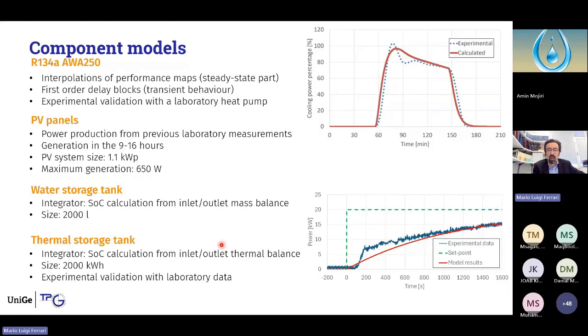For the water storage tank, it was 2000 liters, and on the basis of an integrator that we implemented, we have the calculation of the state of charge from the inlet-outlet balance. Then for the thermal storage tank, the same, for the hot water for the cooling side, for 2000 kilowatt hour in this case. Here on the right side of the slide, you can see a comparison of the model results with the experimental data. For sure, it's not possible to recalculate the specific oscillating behavior that we have at the beginning of the startup. However, we have set the delay components correctly to have the correct calculation of the generic transient trend that is very important for what we would like to do.